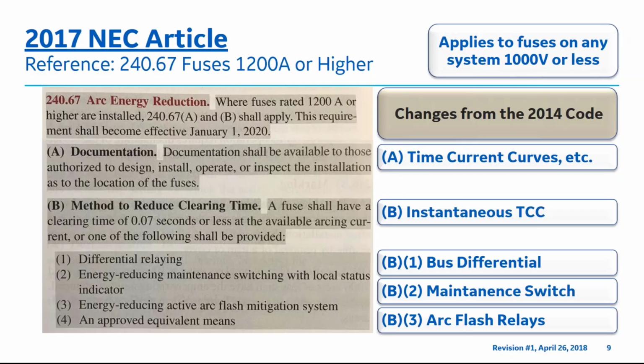Paragraph B, method to reduce clearing time. In this paragraph, please notice that the NEC is specifying that a fuse shall have a clearing time of 0.07 seconds or less at the available arcing current, which would represent the instantaneous region of the time current curve. B1, differential relaying or bus differential. B2, energy reducing maintenance switch, or in other terms, a maintenance switch.